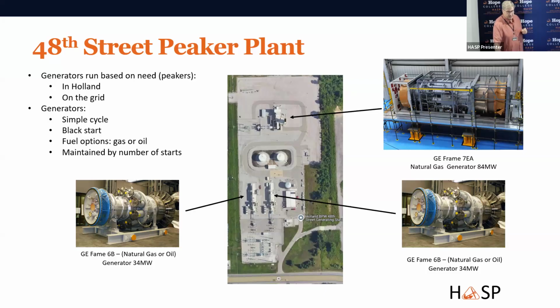We sell electricity on the grid, and we have an overabundance of generating capacity right now. In the pricing of the market, we know how much it costs to generate a gigawatt or megawatt out of Holland Energy Park. Those units are licensed by hours of operation, but these peaker generators are licensed by number of starts. So if after 1,000 starts you have to do maintenance, whereas on the other ones it's after maybe 10,000 hours. So there are two different ways of measuring them, and every time we start one up, that's getting closer to requiring maintenance, so we know the cost implications.